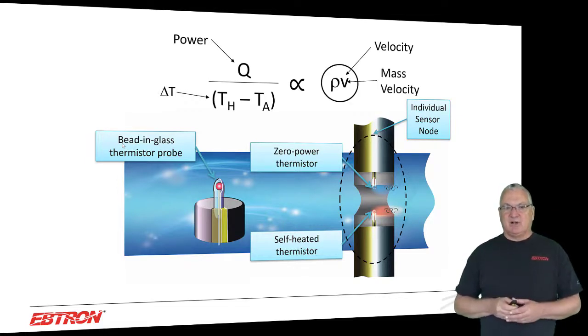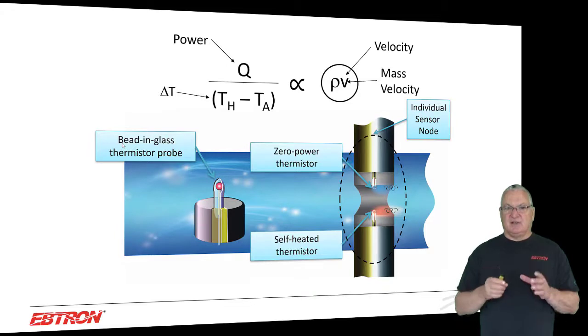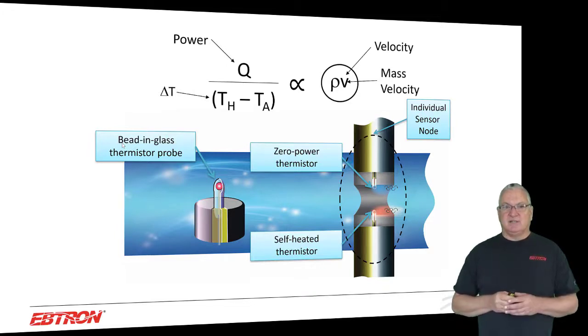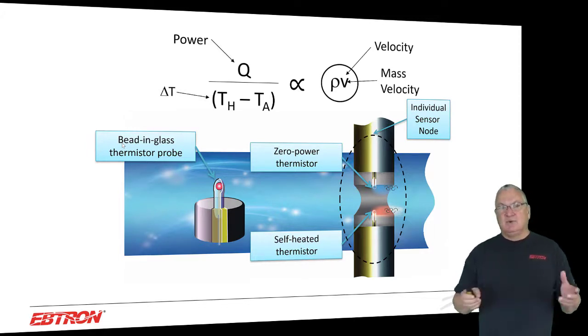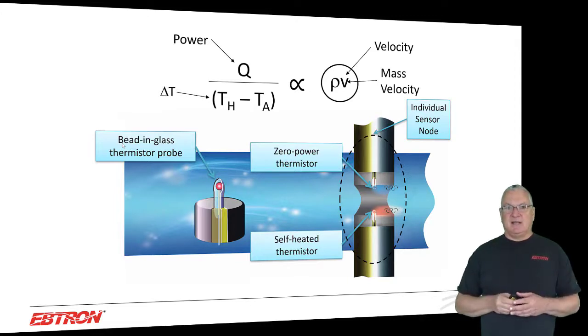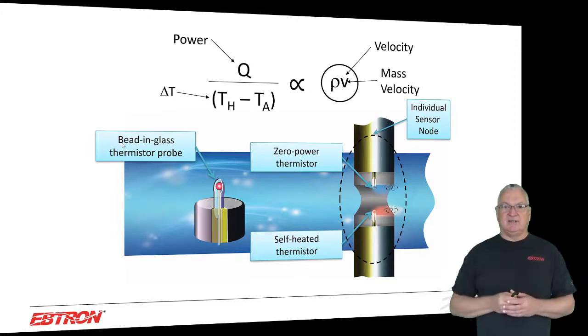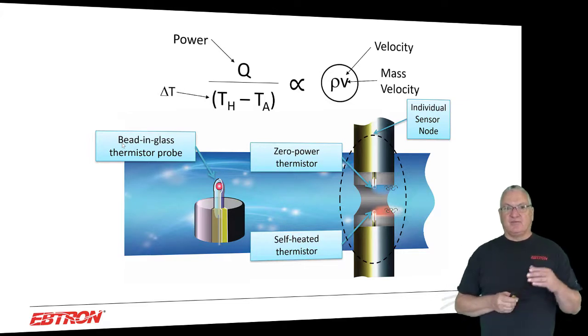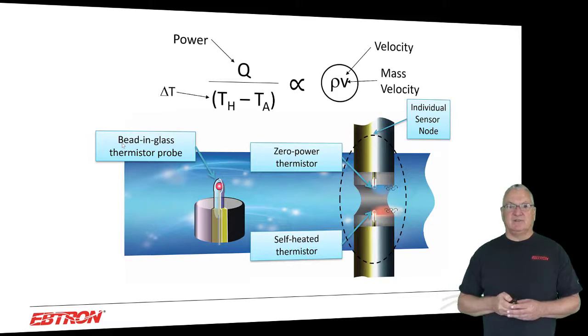And when you look at the EBTRON product, if you look at the illustration there on the right, that's one of our probe tubes. And in each one of our sensor node locations, there's two thermistors. One is self-heated. We pass a little bit of current through to heat it up above ambient. The other one we call a zero power thermistor, which is basically a thermistor that's maintained at near ambient conditions. There's no real self-heat. And so from the two, we can get the delta T, and from the one that's heated, we can determine what the power is, and that's really the main thing that we need to know to make an airflow meter, a thermal airflow meter.